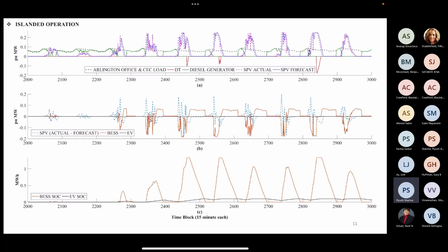So these are the results over a larger time series. We can see that during certain instances, power had to be sent back to the grid during this particular time period. I mean, it's assumed that it's sent back to the grid, but during these periods, essentially the solar had to be curtailed because the SOC associated with both the EV and the battery reaches its maximum value. So no further power can be absorbed, and the solar generation is significantly more than the load. So either the solar generation has to be curtailed, or if feasible, it has to be sent back to the grid.